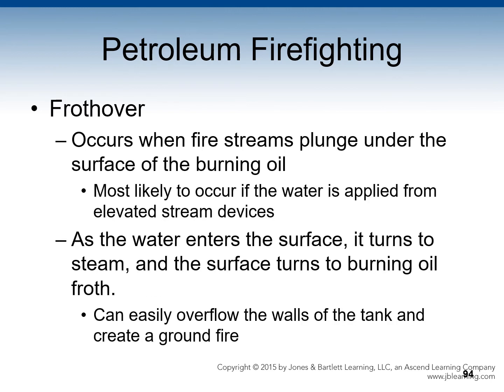Froth over occurs when fire streams are directed at an angle that plunges under the surface of the burning oil. This would most likely occur if the water were applied from an elevated stream device such as a ladder truck. As the water enters the surface, it turns to steam, much like the boil over, and the surface is turned to burning oil froth. This froth can easily overflow the walls of the tank and spread as a ground fire.